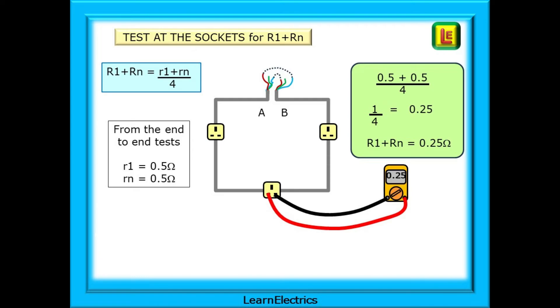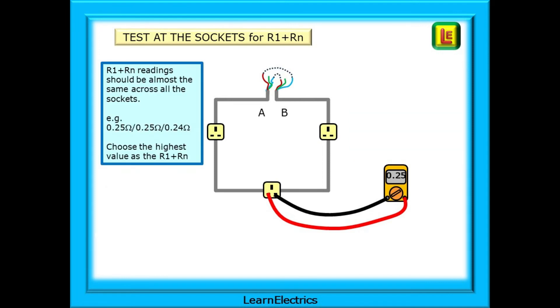Inserting the end-to-end test results for little R1 and Rn into the formula, we should expect our test meter to return similar readings of about 0.25 ohms. By doing this calculation, we are double-checking that the readings are correct and also checking that the circuit is wired correctly. Big R1 plus Rn readings should be almost the same across all the sockets. For example, 0.25 ohms, 0.25 ohms, 0.24 ohms.